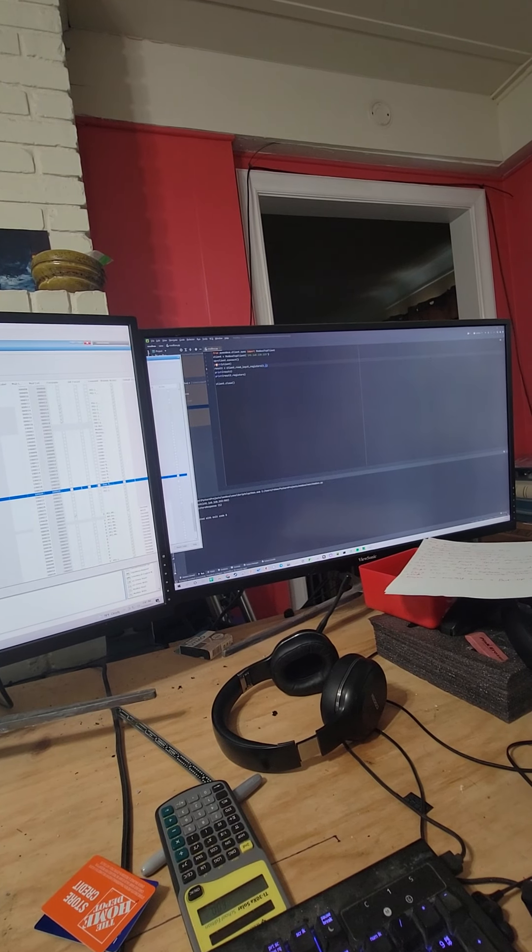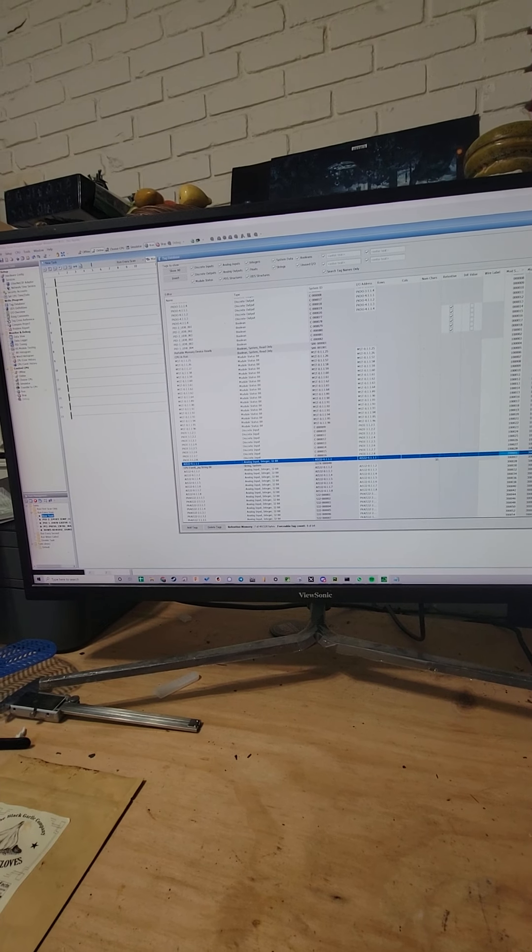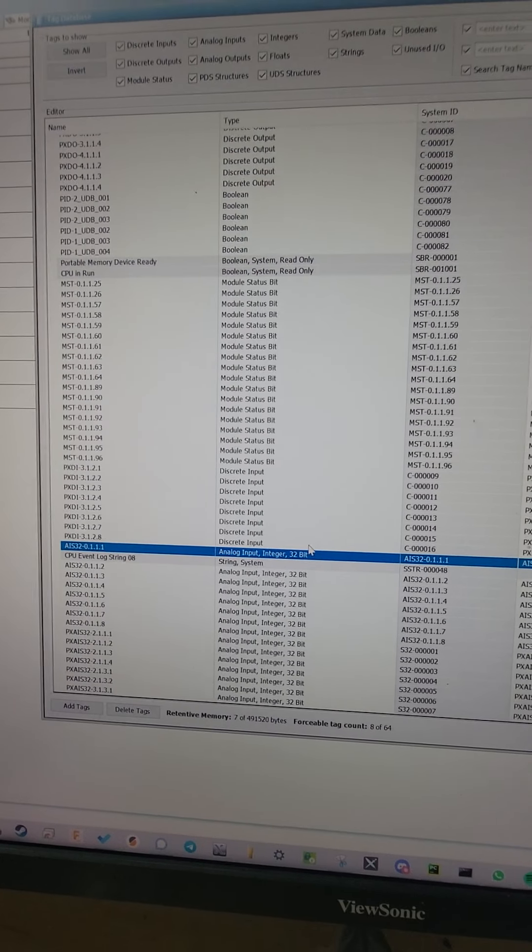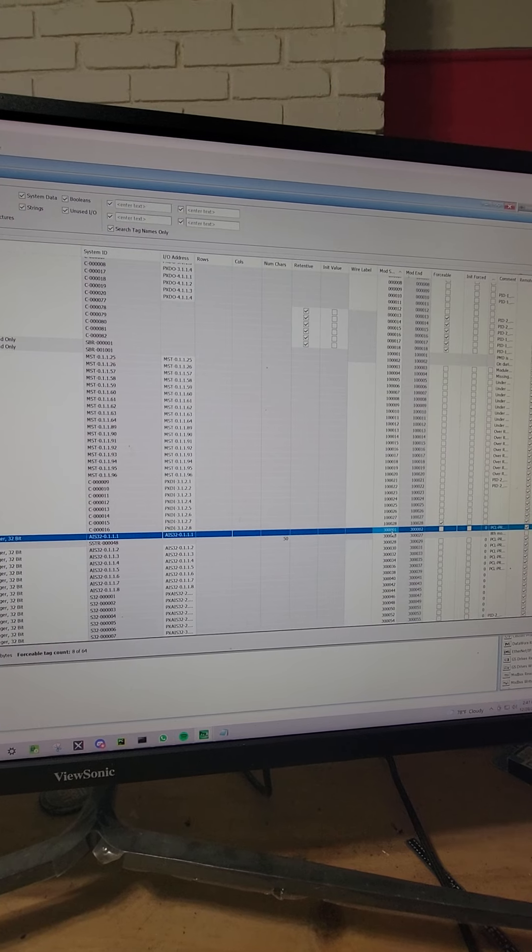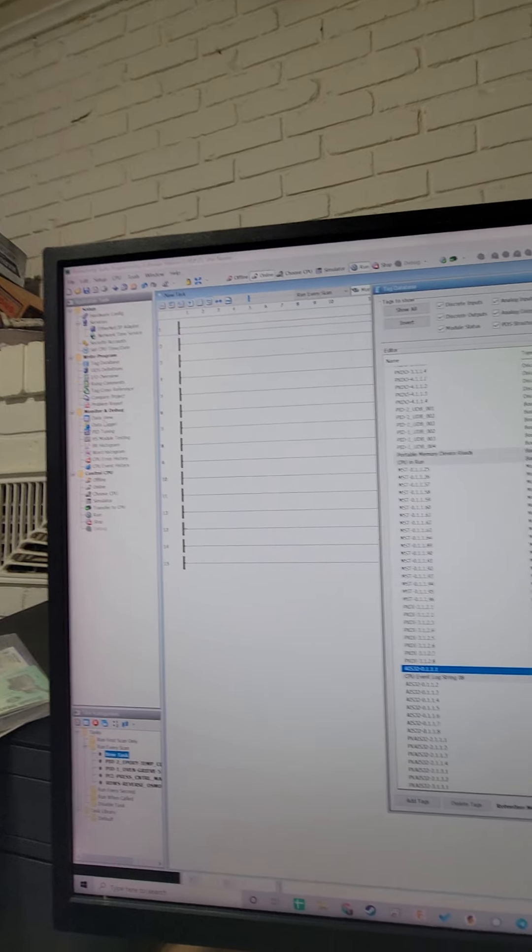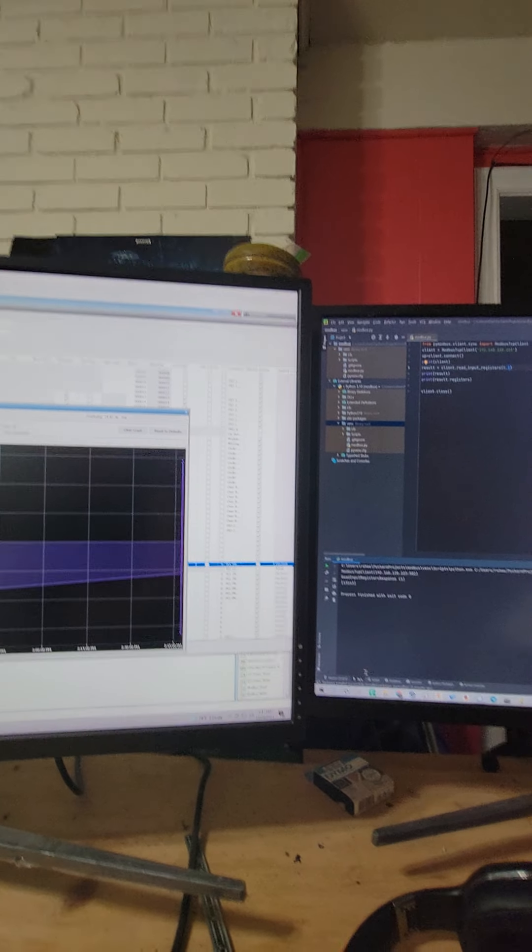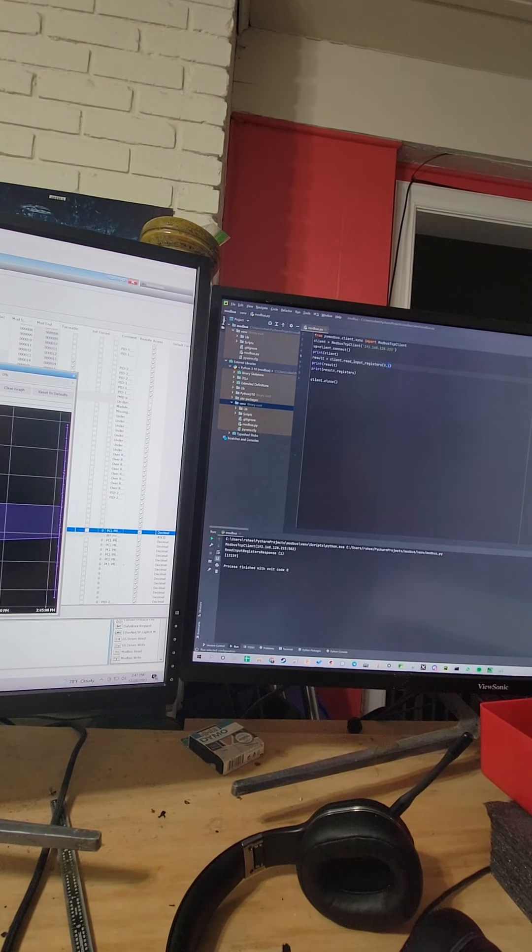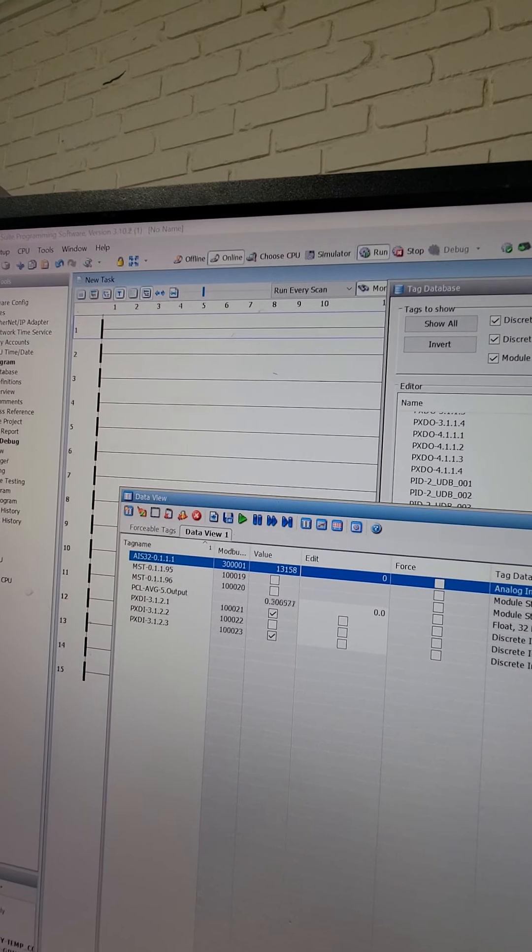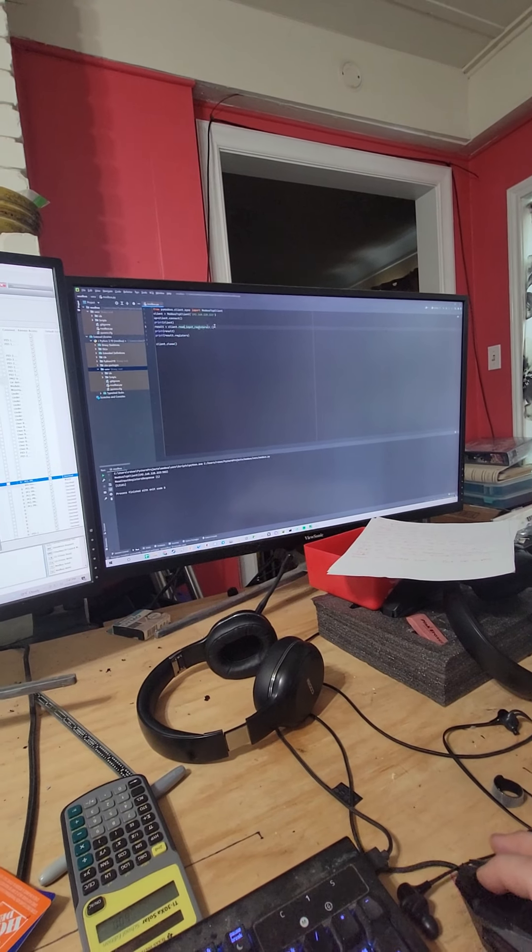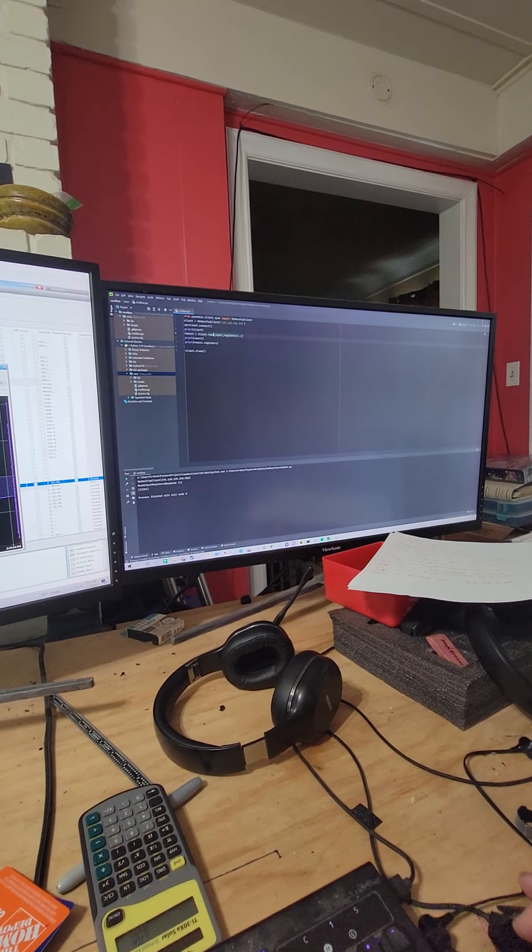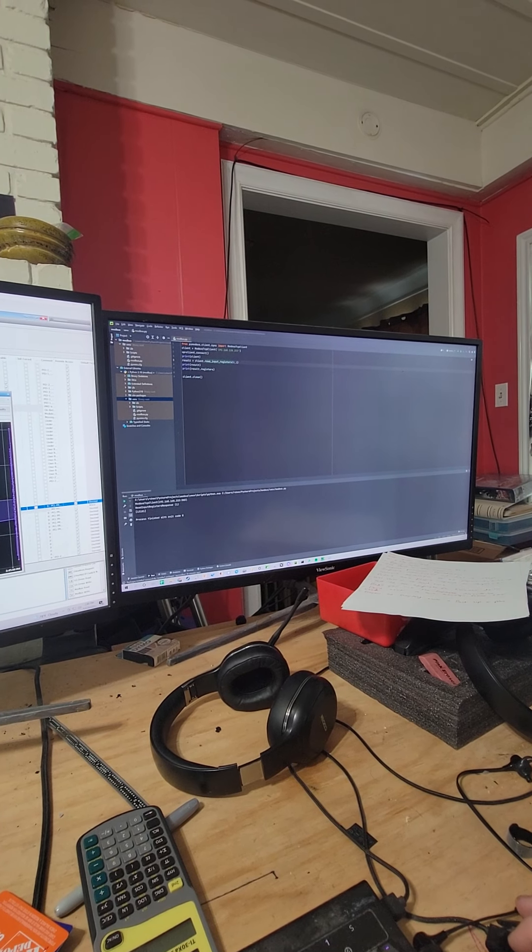Inside of PyModbus it's actually going to be off by one. So 20 will be 19, 21 will be 20, etc. because we're going to start at zero. Right now I am pulling this one here, which is AIS 32 0.1.1.1. That's the analog input. It's a 32 bit integer and it is at address 3001. So whenever I go to data view in the PLC, I have that one up so you can see it's changing a lot. If we run this script a couple times we'll see 13159, 13181, and you can kind of see that it's changing about that much on the PLC.